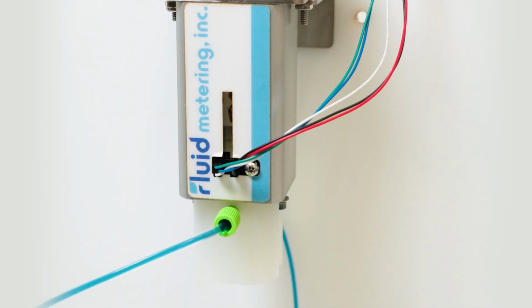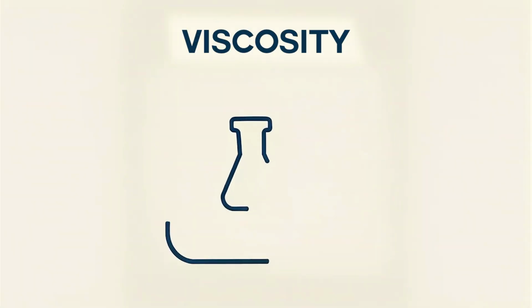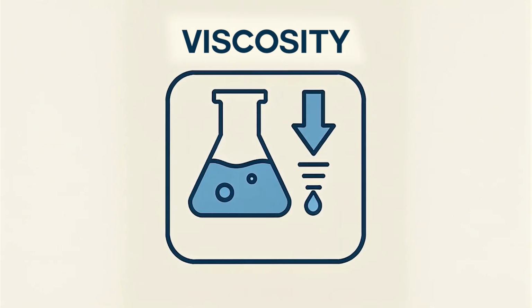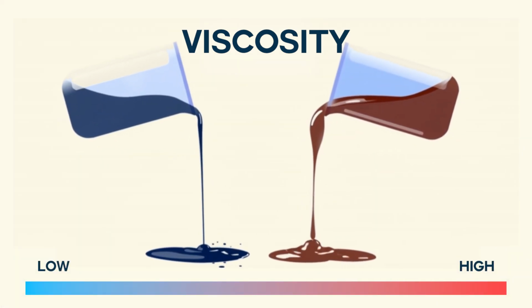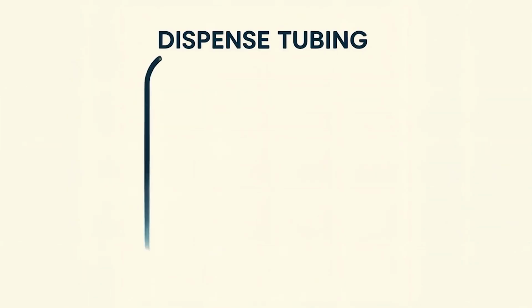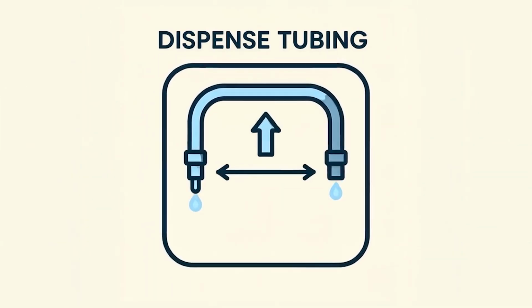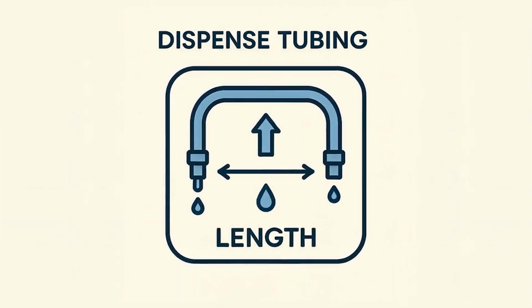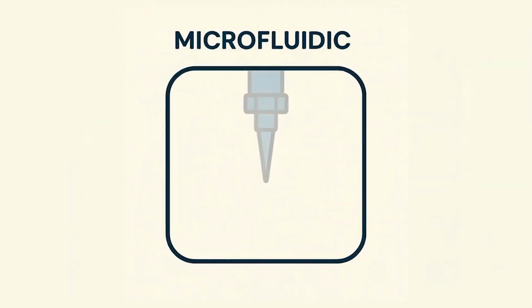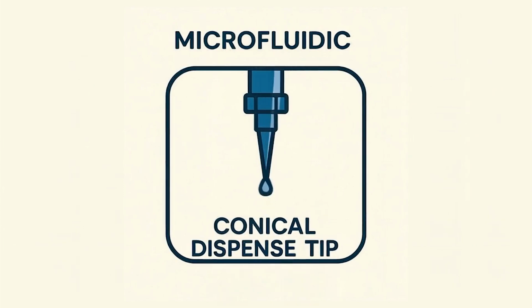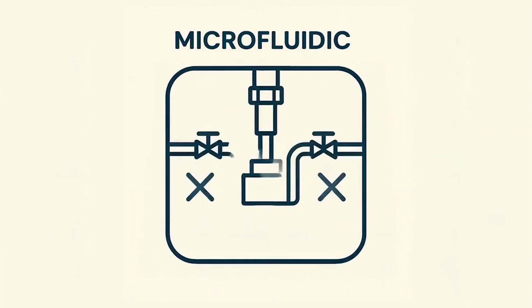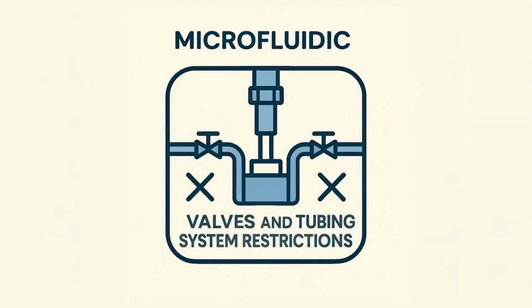Pump performance can also be influenced by a few system variables. Fluid viscosity is the first one. Thicker fluids require more torque to move, and you may need to increase your run current to keep your pump operating smoothly. Tubing length is another factor. Longer tubing adds resistance, which can affect pressure stability and overall accuracy. Your dispense tip design also matters. Narrow tips can create pressure spikes, while wider tips may reduce your precision. And finally, any system restrictions, such as valves, manifolds, or long tubing runs, can introduce back pressure that impacts the pump's performance. Keeping these variables in mind will help you fine-tune your setup and achieve the most consistent results.